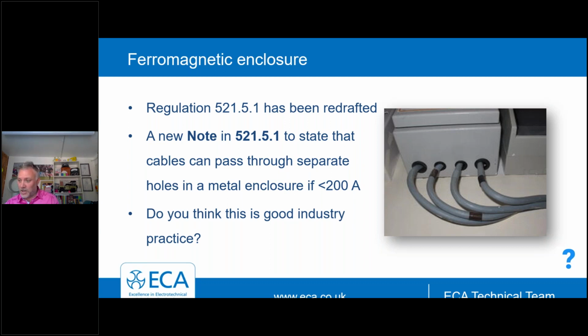The ECA concerns here: are manufacturers going to verify their enclosures for all situations, so for frequencies other than 50 hertz, taking into account heating effects and harmonics, especially renewables on our networks? Will this cause future problems when demand is placed on the installation? So it may be okay today, but when more demand is put on that network tomorrow, is it going to cause some problems? We believe at the ECA this is actually poor practice, and we'll be really interested in what your thoughts are too.